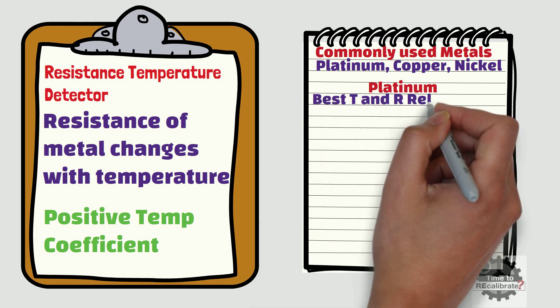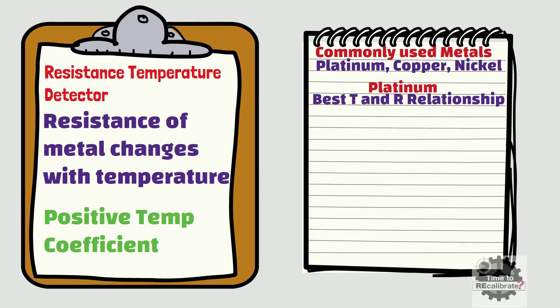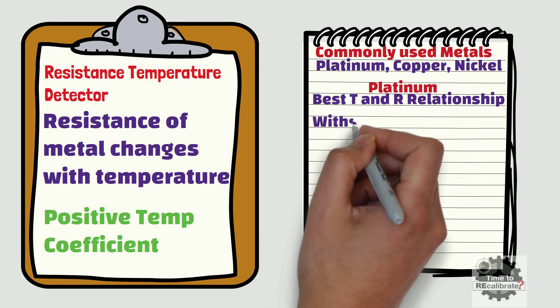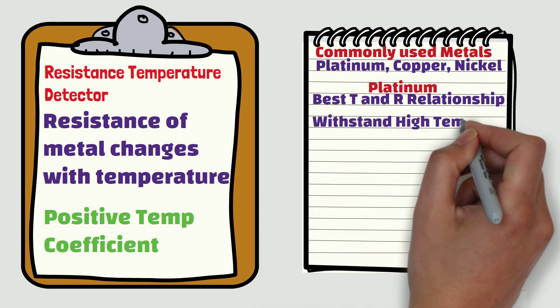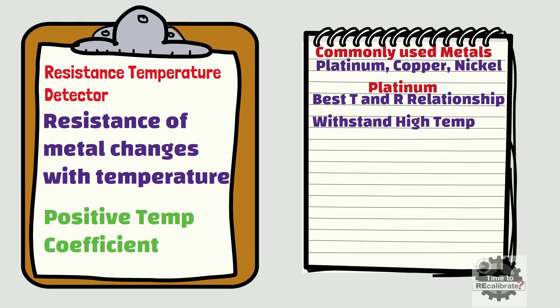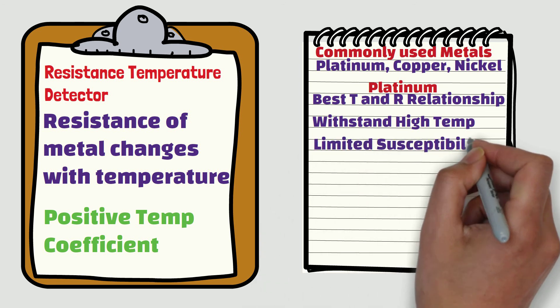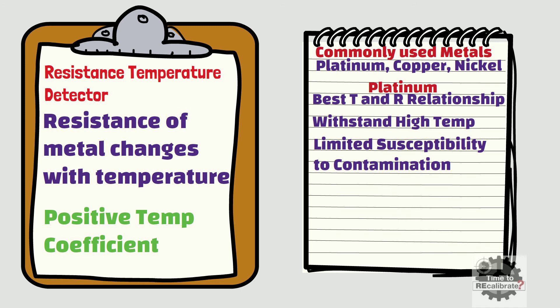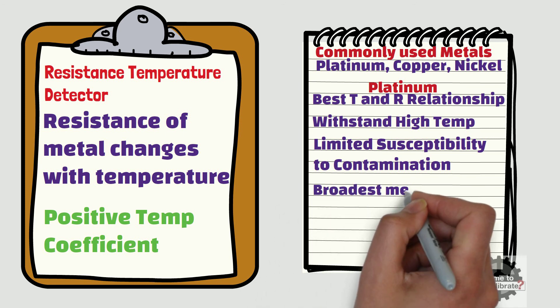This is because it has the best temperature to resistance relationship. Secondly, platinum is also popular because of its limited susceptibility to contamination. Lastly, platinum has the broadest measuring range.